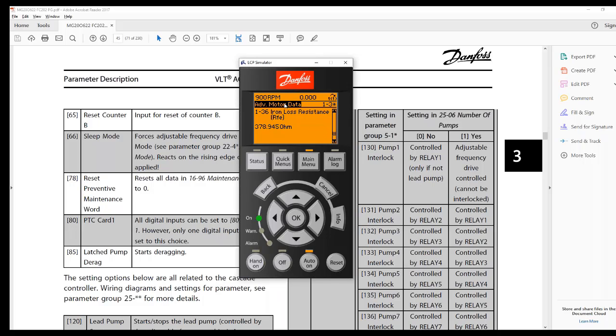So when you set the basic motor parameters, the drive will take a default motor model. So these numbers will change just based on basic motor tuning and stuff, mostly Euro motors, I'd say, because it's a Danish design. But when you do AMA, it corrects these numbers for real live data then. And these numbers are used to tune the output of the drive to give the motor exactly what it needs at different power levels, at different voltages and different frequencies.